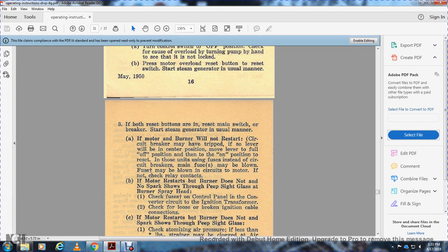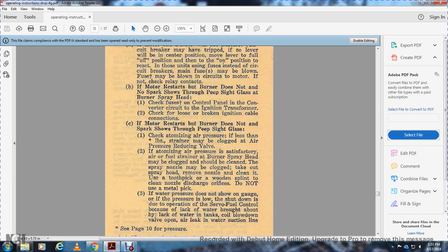If the motor restarts but the burner does not spark, peep through the sight glass at the burner or the spray head. Check the fuse with the control panel, the converter circuit, and the ignition transformer. Check for a loose or broken ignition cable connection. If the motor restarts, the burner does not light, and the spark shows through the peep sight glass, check the atomizing air pressure. See page 10, pressures. The strainer may be clogged.